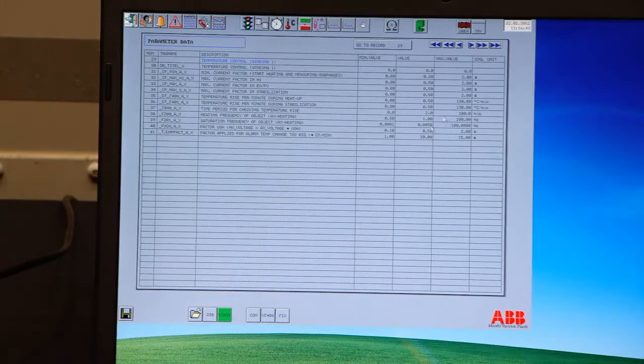So what we have now is that we have set the current factors. So we are heating at minimum 20% of nominal current. We are heating at maximum 50% of nominal current. We have the frequency. We are nominally heating at 1 Hertz. We have an updating time of the temperature rise of 2 minutes. And we have an expected heating at 0.5 degrees per minute. That's kind of the parameters that are controlling how the converter will perform.